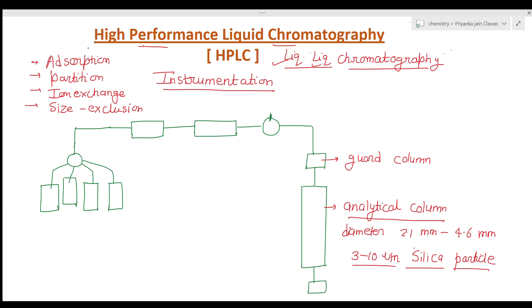A liquid phase is coated upon these silica particles, and that coating makes the stationary phase. So in the analytical column — made of stainless steel, diameter 2.1 to 4.6 mm — porous silica particles of 3 to 10 micrometers are used as the packing material, coated with the liquid stationary phase.